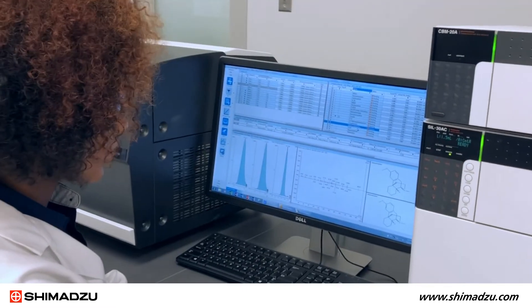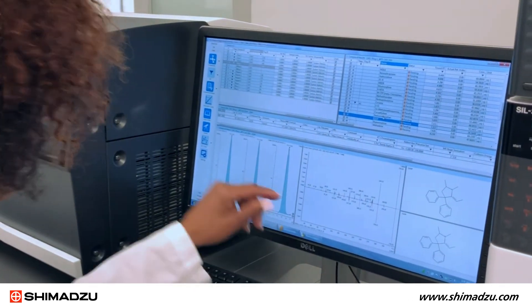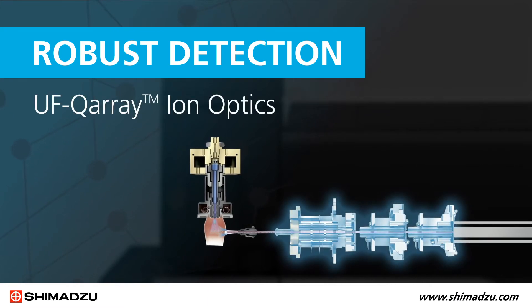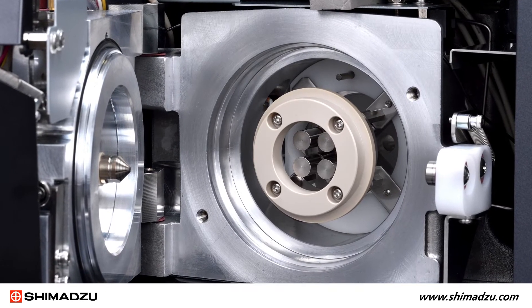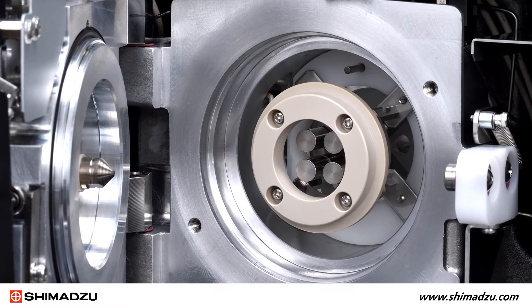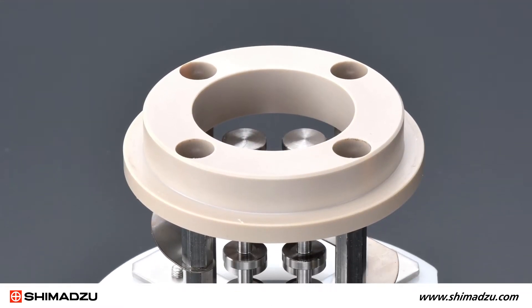In order to measure MRM transitions in very short times, you need very high sensitivity. So we developed our UF-Qarray ion optics technology to enhance LCMS instrument sensitivity. UF-Qarray is an ion guide based on a high frequency quadrupole electric field with a high central convergence. It improves ion focusing efficiency to achieve higher signal intensity.